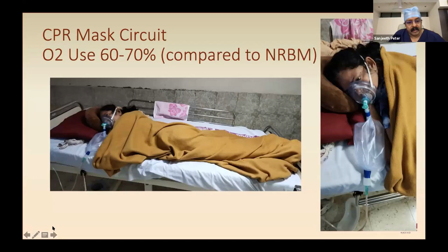If that fails and you need to go on to a CPAP or a BiPAP, we use this circuit where we attach an oxygen port as a piggyback. Again, we use a fitted mask. This is a single limb circuit. There is no exhalation limb in the original circuit, but we add on an exhalation limb. The exhalation limb, with the ones that are supplied, is usually either in a slit near the mask or the side of the mask, and there is no protection to HCWs.